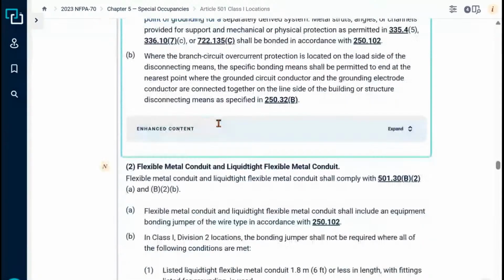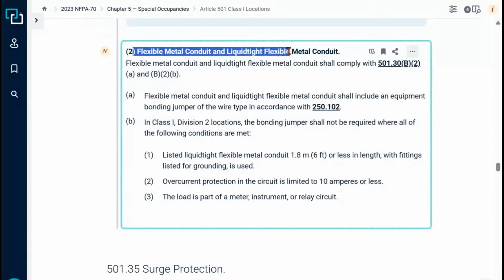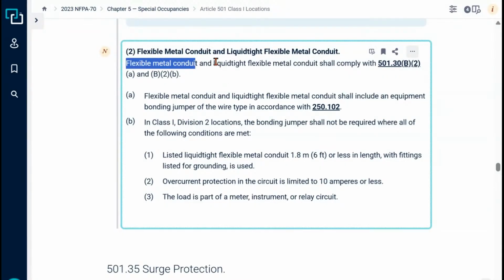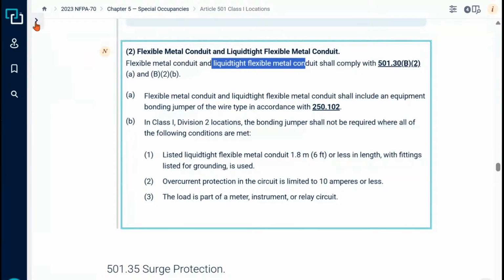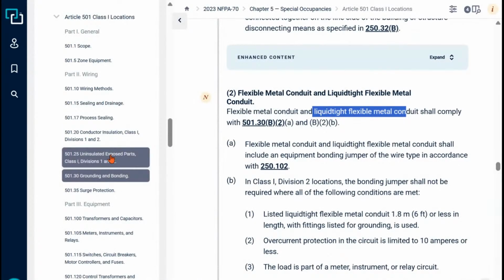So in our case, since we were talking about flexible metal conduit and liquid tight flexible metal conduit, which we'll go back and look at in the wiring methods for a second, it says that if you use FMC or LFMC, then you have to comply with these bonding requirements, right? Makes sense, right? So you see how these interconnect and work together. And this is going to make reference to using the equipment bonding jumper requirements in 250.102, right? And so we'll go look at that. But what I wanted to show you is the wiring methods, since we kind of jumped to it and people get confused with it.